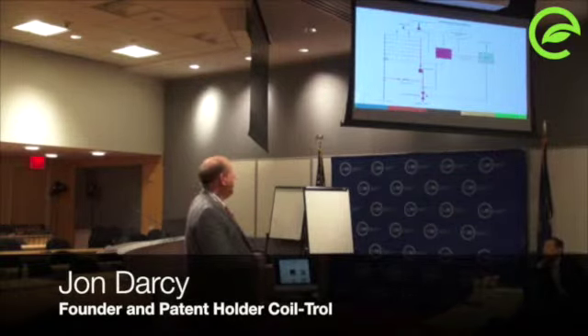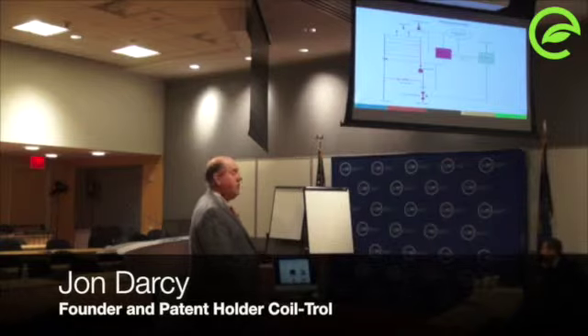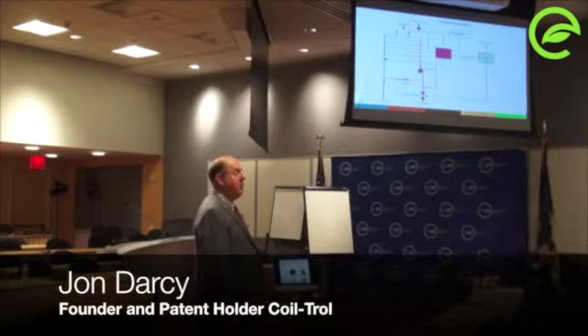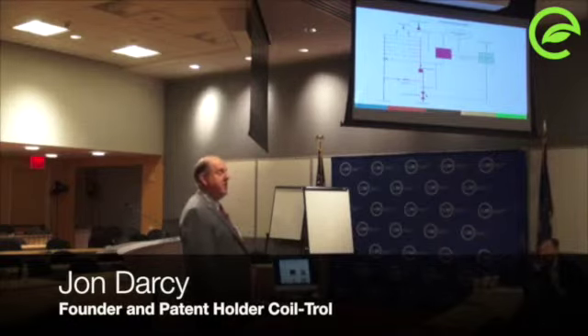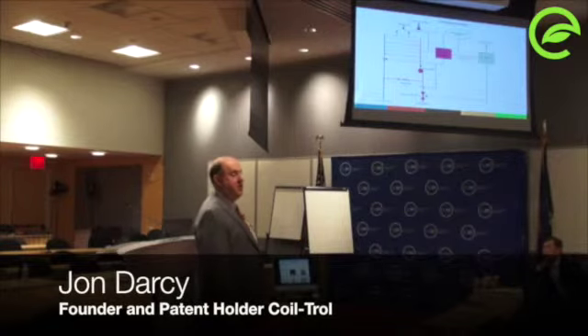The only problem you can have is if you start running the thing, if you try to creep too much out of it, you could theoretically get the flow down below the minimum flow for the chiller, and then the bypass valve has to open on the chiller, back to the system, so that you're maintaining a minimum flow through the chiller.